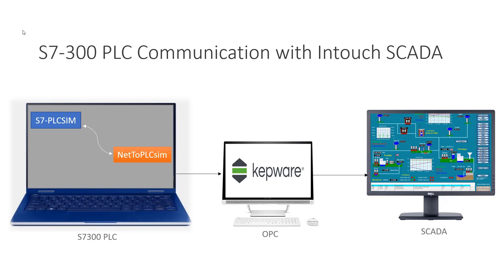All you need is Simatic Manager installed and Net2PLCSim software. The purpose of Net2PLCSim is to give the OPC server the feel of a real PLC connected to it, so it won't look like a simulator. If you directly try to connect the PLC Sim simulator (S7-300 Simatic Manager simulator) to Kepware OPC, it will not work — you must have Net2PLCSim installed on the same system.